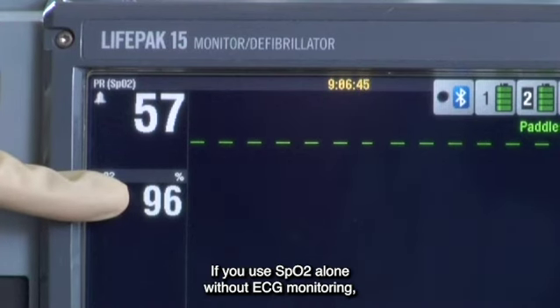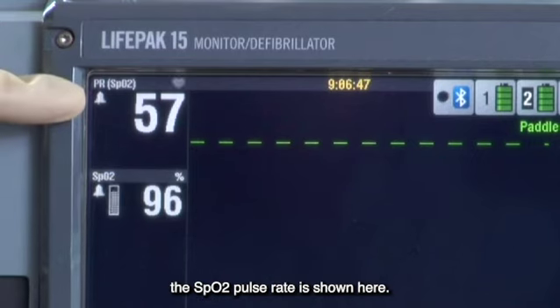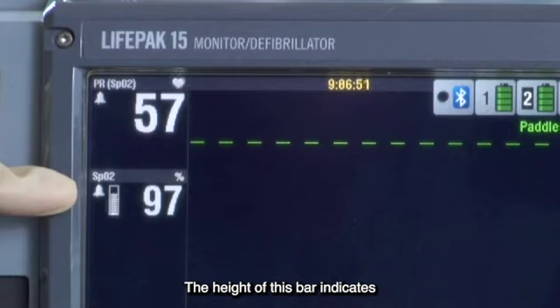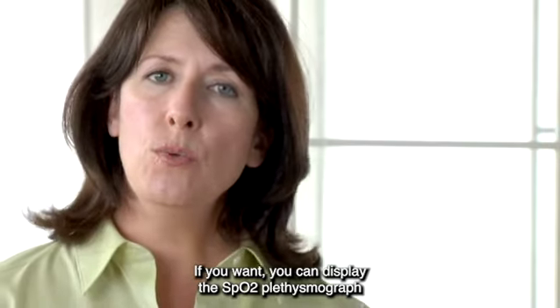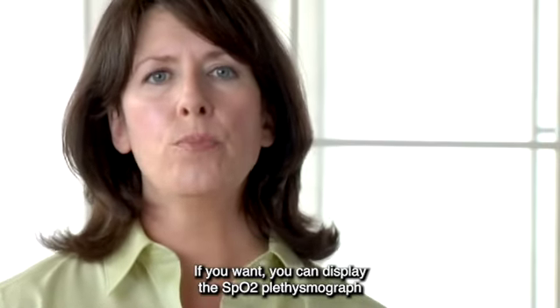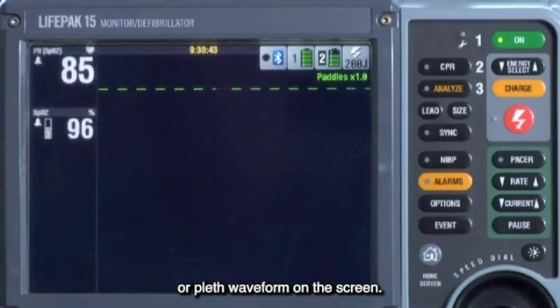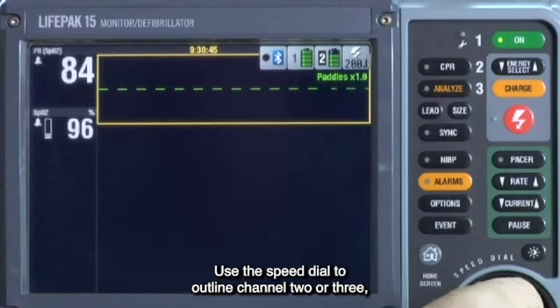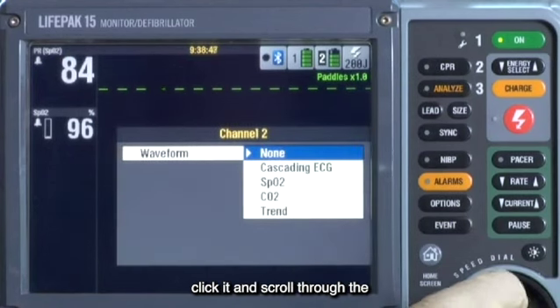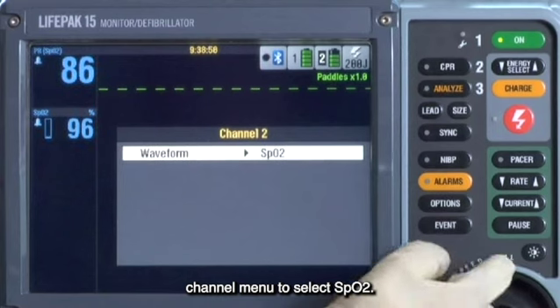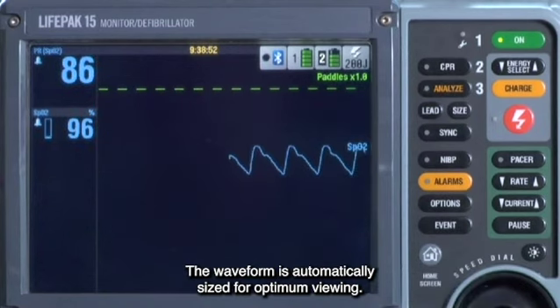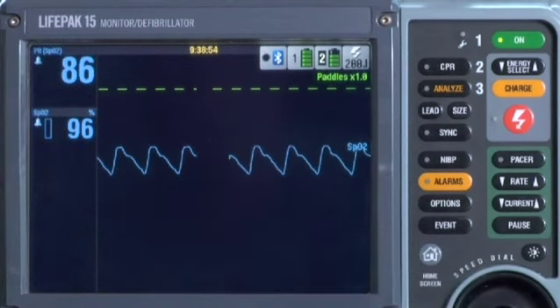If you use SpO2 alone, without ECG monitoring, the SpO2 pulse rate is shown here. The height of this bar indicates the quality of the signal. If you want, you can display the SpO2 plethysmograph, or pleth waveform, on the screen. Use the speed dial to outline channel 2 or 3, click it, and scroll through the channel menu to select SpO2. The waveform is automatically sized for optimum viewing.